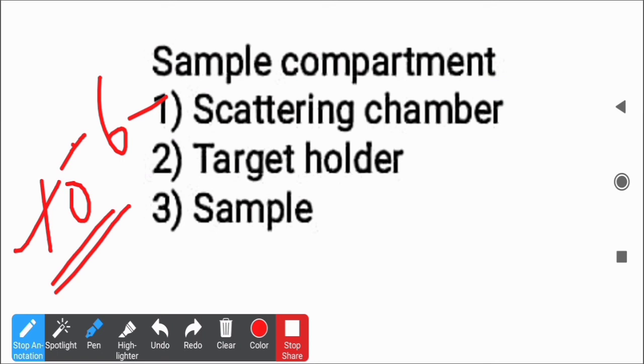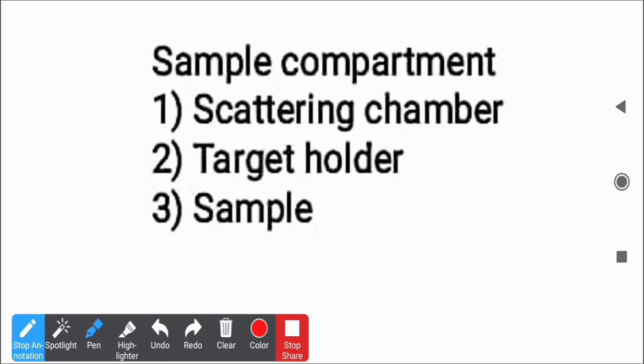Okay, so the requirement of the instrument is fulfilled in such a way that the target holder is made rotating, so that the samples placed at different positions can be analyzed within a single take. The target holder assembly is usually of the ladder type, made of stainless steel with equidistant holes in it. Okay, so we might use a circular disc type target holder, or some ladder type stainless steel strips having holes in them. So the target holder is of two types: circular or ladder type.